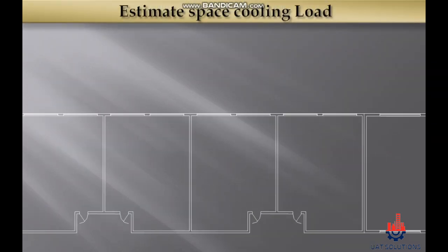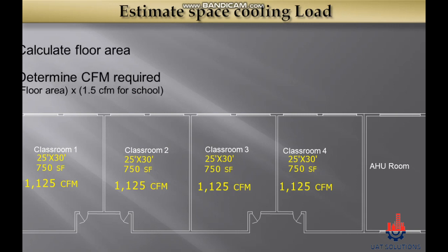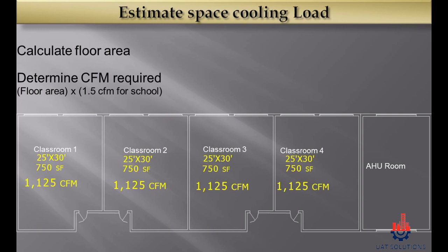Let's calculate the space cooling load using the formula we just discussed. Classroom 1 has a floor area of 25 by 30 feet, making it 750 square feet in total. We will get the cooling load by multiplying 750 by 1.5, which equals 1,125 CFM.